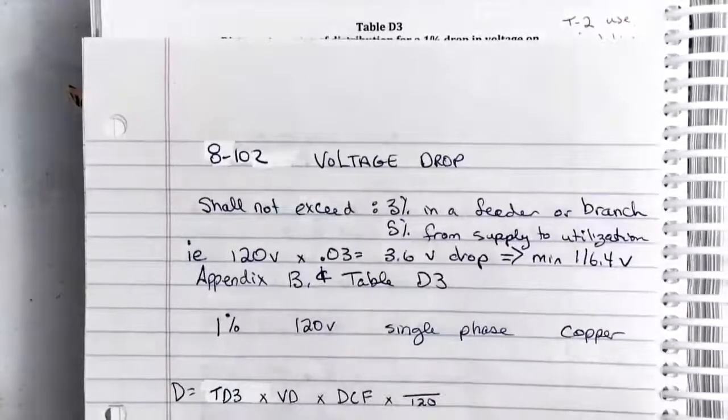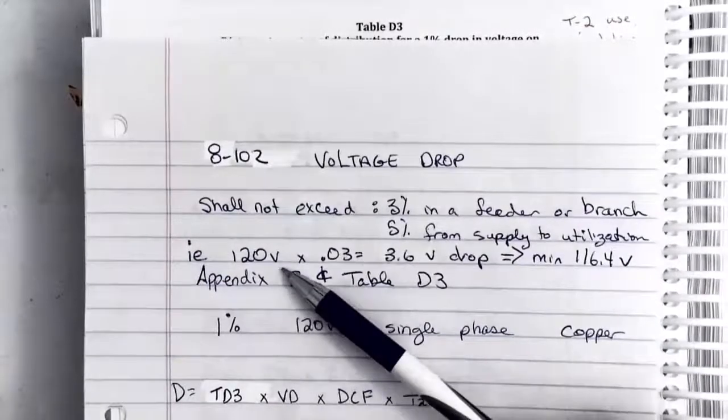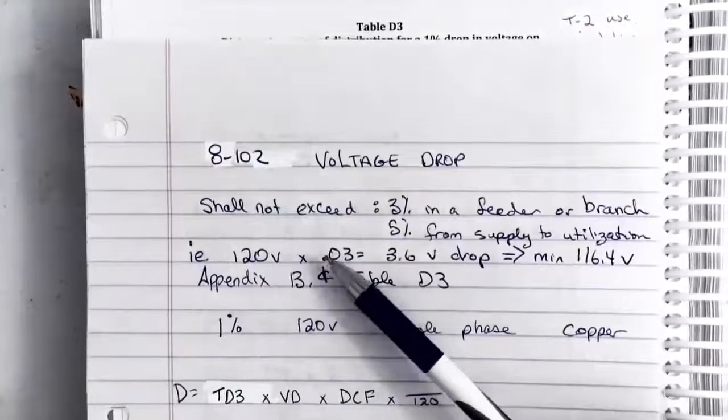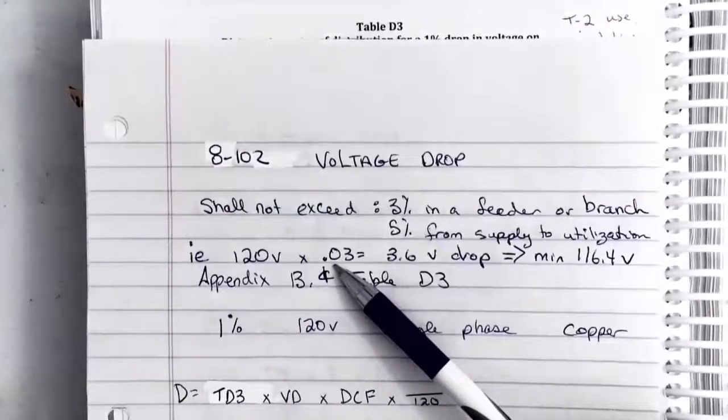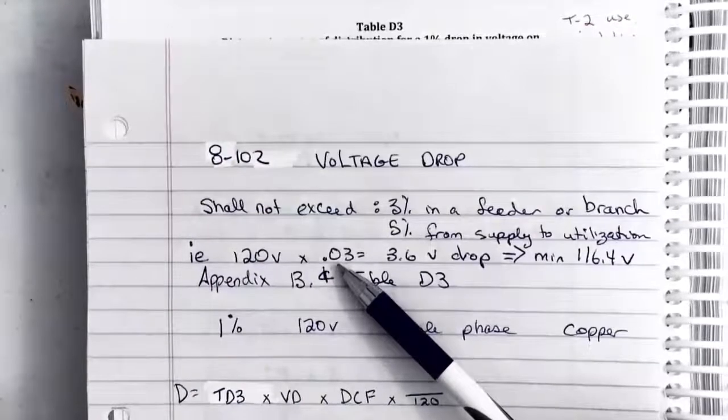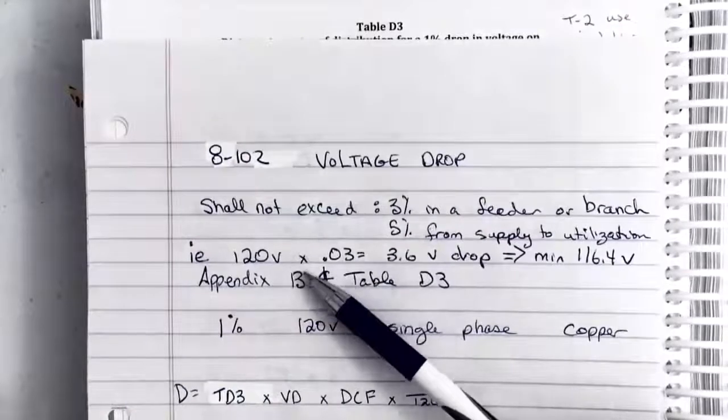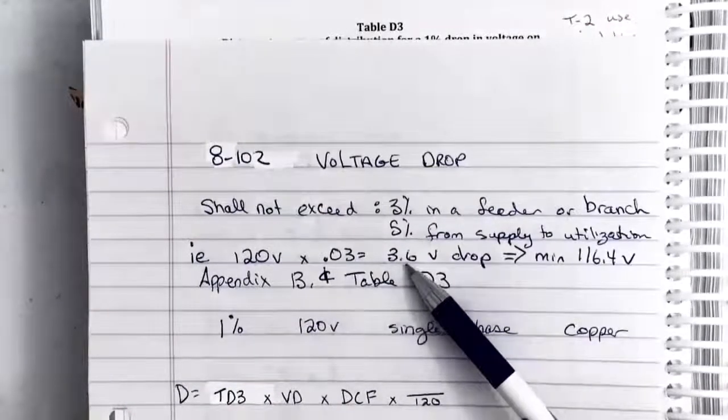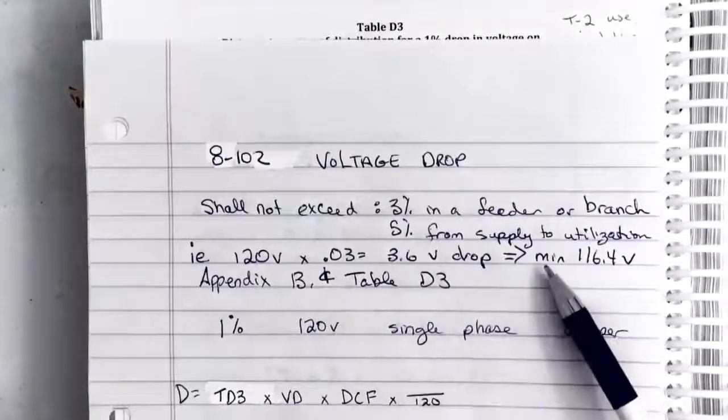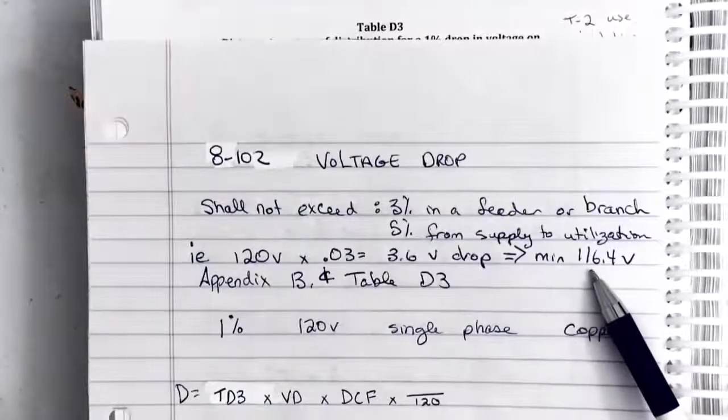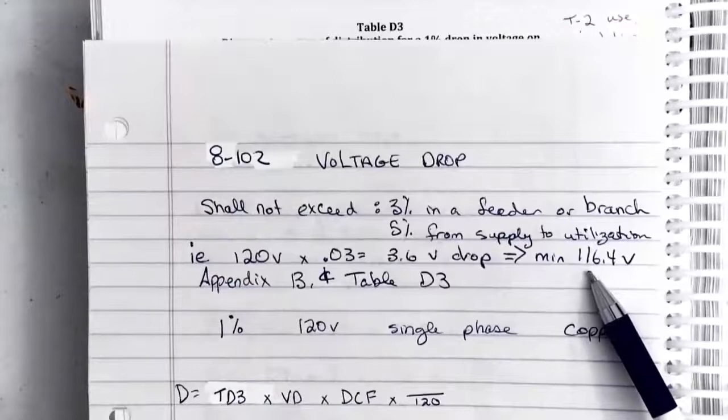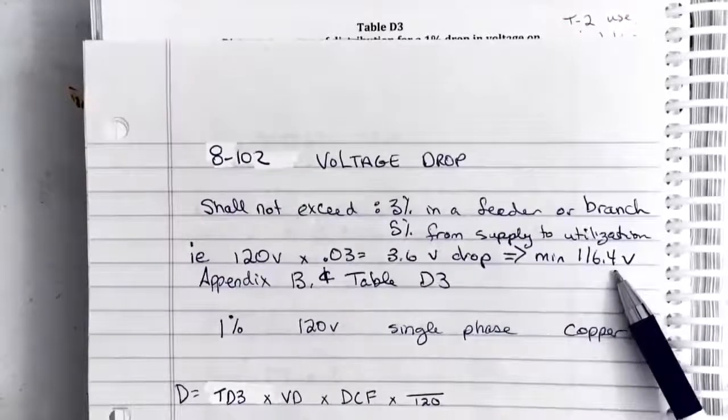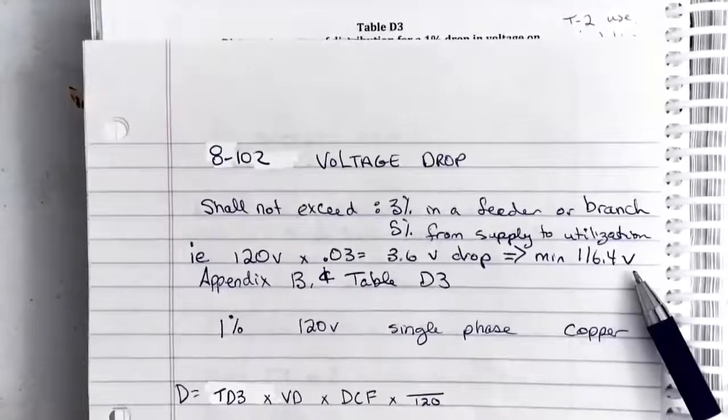What does that exactly mean? Well, let's say we had a 120 volt supply. The maximum amount of voltage that we would be able to drop in the lines getting out to the load would be 3%. So 120 times 0.03 gives me a maximum of 3.6 volts drop. That means at the load we would end up getting a minimum of 116.4 volts supplied to the load.